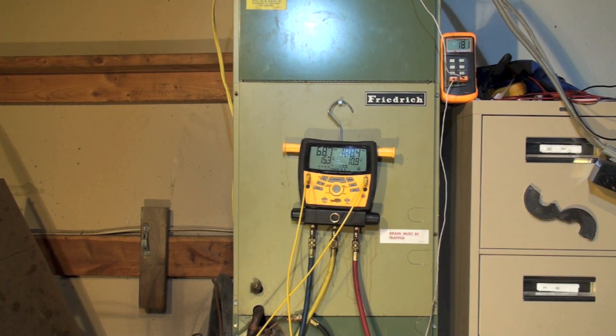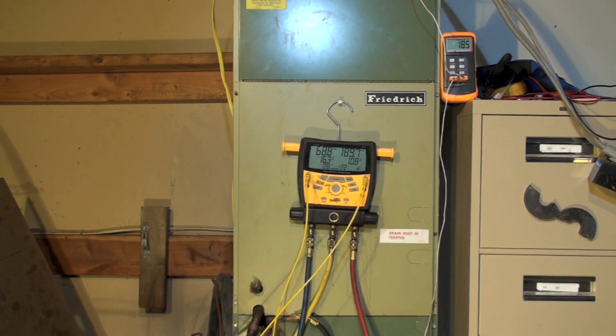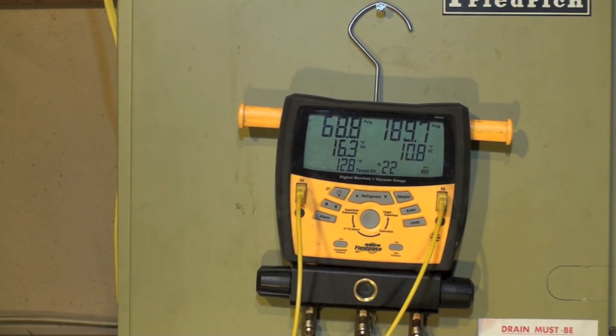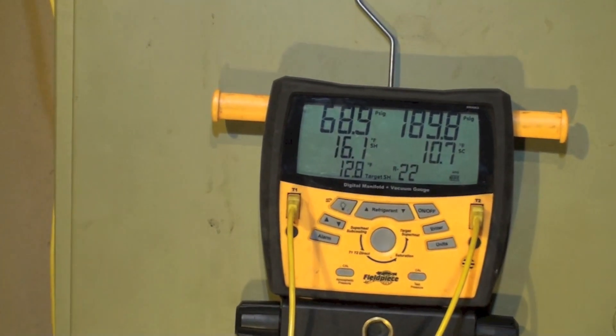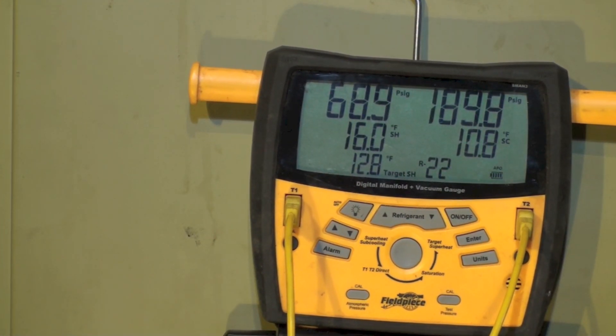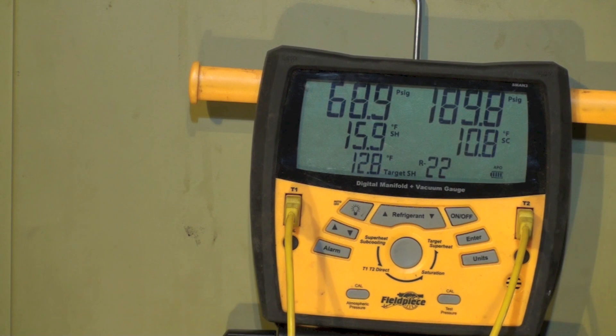Okay we have a target superheat now of 12.8. Our superheat went up a little bit. Showing 15.9 right now. So we're still a little bit off. Let's see how much refrigerant it takes to get that to target superheat.